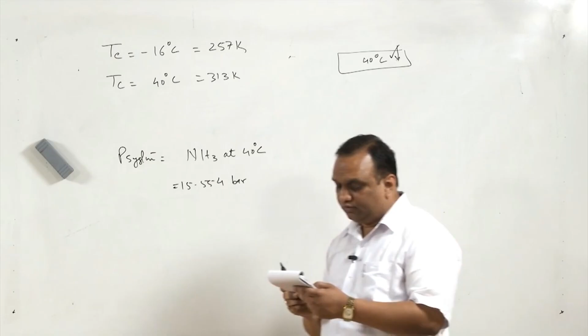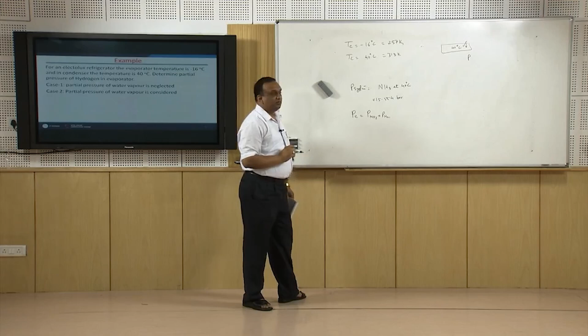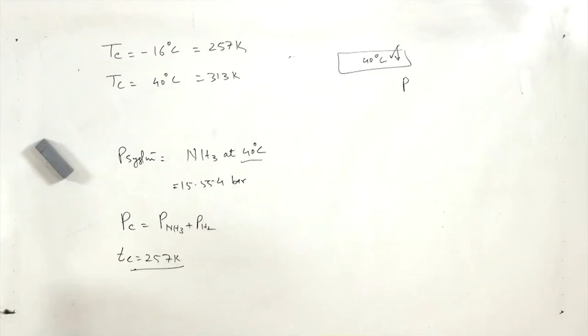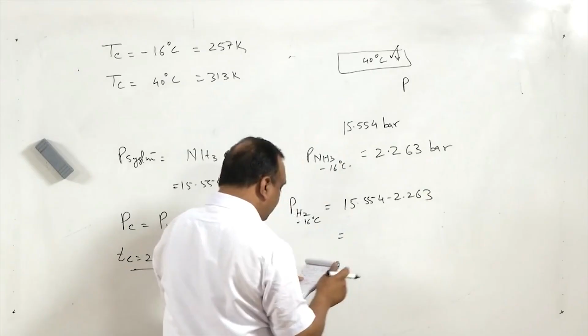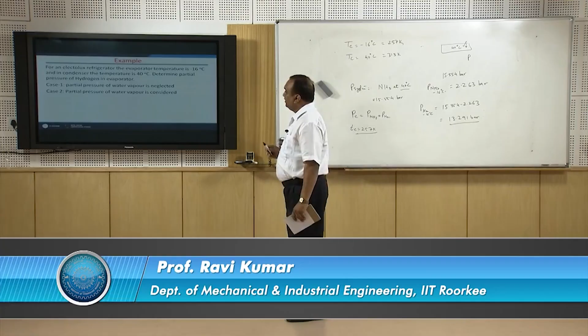Now, if we go to the evaporator, case 1, partial pressure of water vapor is neglected. The total pressure in the evaporator is equal to the pressure of ammonia plus the pressure of hydrogen. But it is not the pressure at 40 degrees centigrade; the evaporator temperature is 257 Kelvin. So, at minus 16 degrees centigrade, the pressure of ammonia and hydrogen will be the total pressure. The total pressure of the system is 15.554 bar, and that is equal to the pressure of ammonia at minus 16 degrees centigrade, which is 2.263 bar, plus the pressure of hydrogen. So the pressure of hydrogen at minus 16 degrees centigrade is going to be 15.554 minus 2.263, which is 13.291 bar.